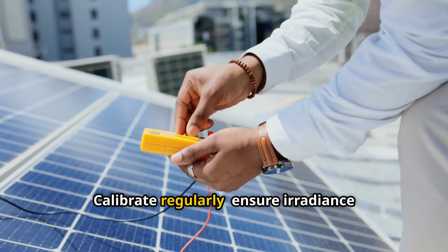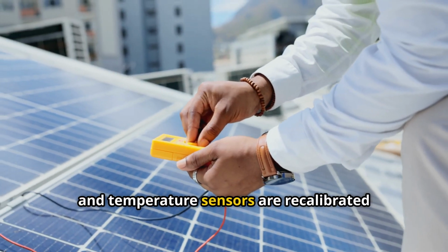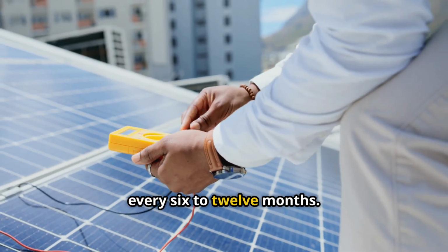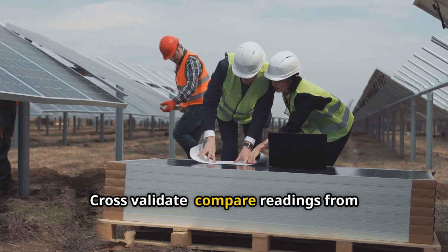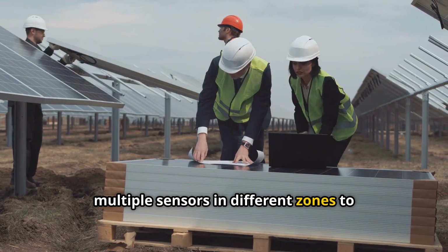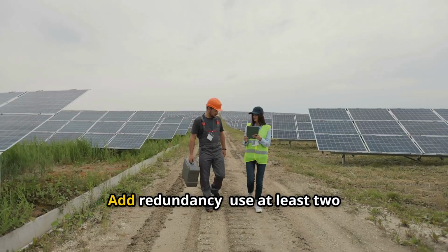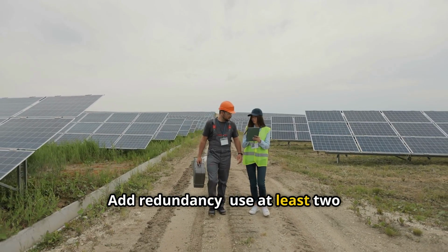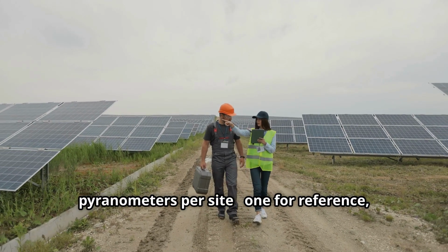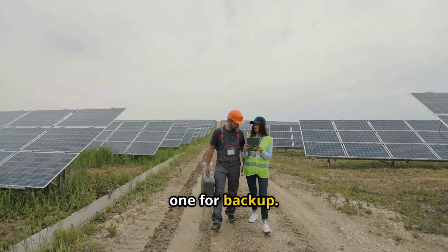Calibrate regularly. Ensure irradiance and temperature sensors are recalibrated every 6 to 12 months. Cross-validate. Compare readings from multiple sensors in different zones to catch anomalies. Add redundancy. Use at least 2 pyranometers per site. One for reference, one for backup.